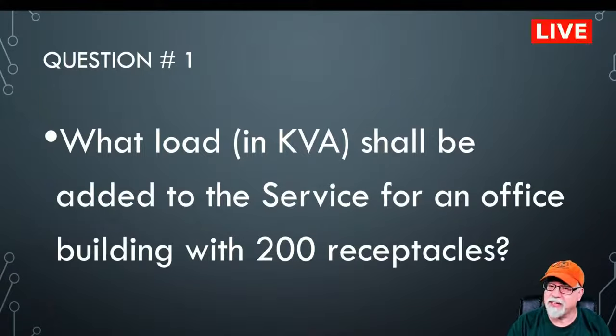You could take the full connected load value of something and run with it, but it's going to mean your services are overly large than necessary. And again, you're not taking into account any diversity, which you can take into account in the National Electrical Code. So when you're taking an exam, always consider, unless it says it otherwise, to resolve the question to the best possible answer. And for us, the best possible answer is the smallest size service necessary to handle the load. Okay, so that is the best possible choice.